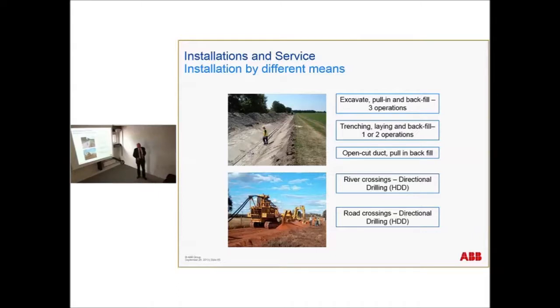That was submarine cables. When it comes to underground cables, onshore cables, there are also a lot of different technologies. You can have an open trench, excavate, pull the cable in and fill back. You can also use directional drilling for river and road crossings, and you can also have what we call a cable plow. You can plow down the cable directly in the ground.